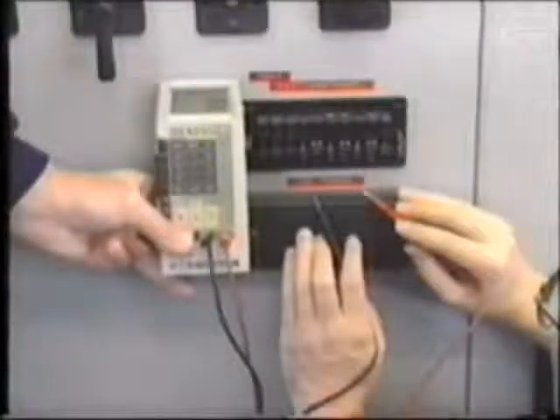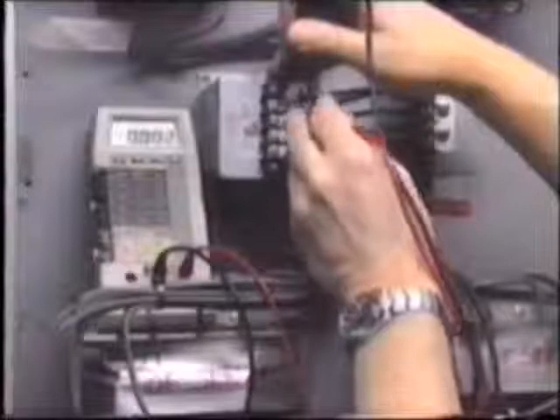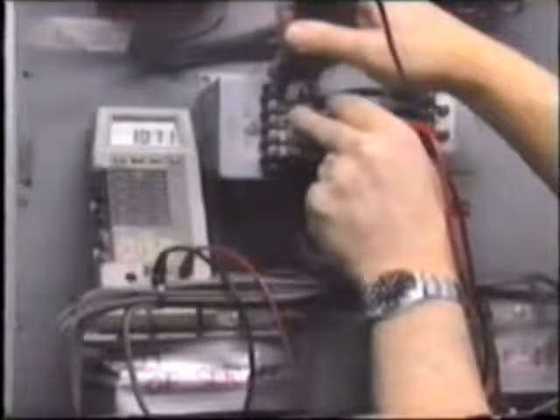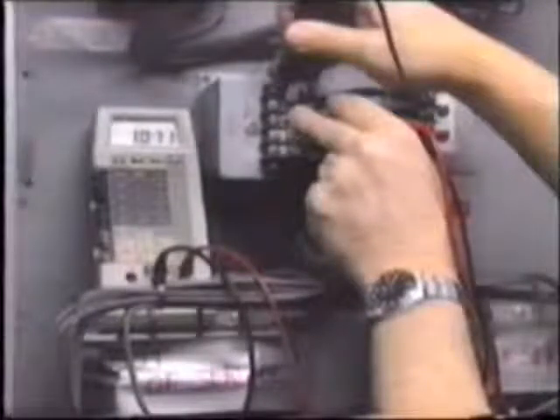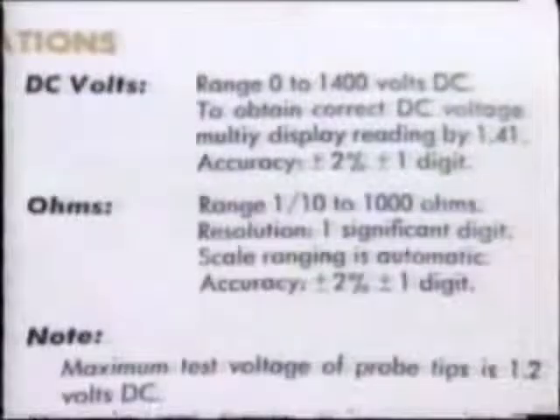For example, when this digital multimeter is selected to measure AC current, we note that the margin of error is specified as 0.9%. This would not be adequate if we are, say, trying to adjust the output of a current transducer within a specified margin of 0.2%. The accuracy of adjustment can only be as good as that of the instrument which you are using for measurement. Consult the specifications when in doubt.